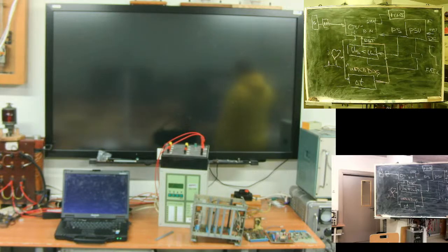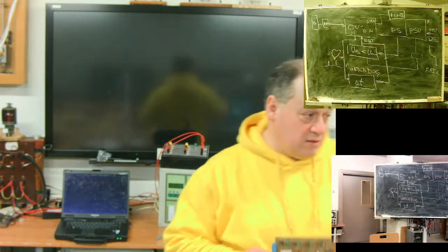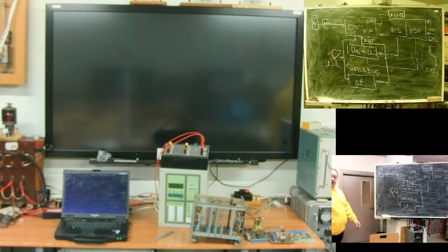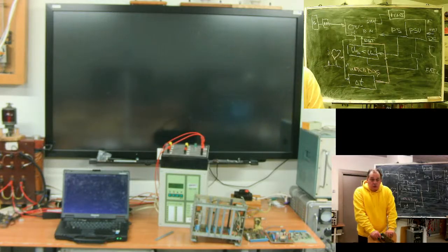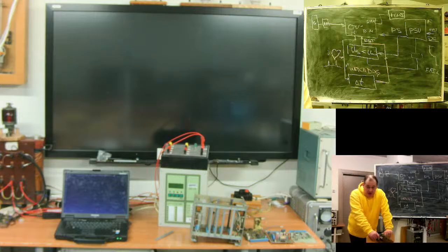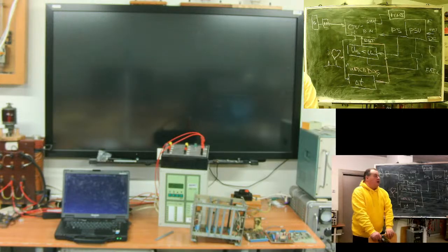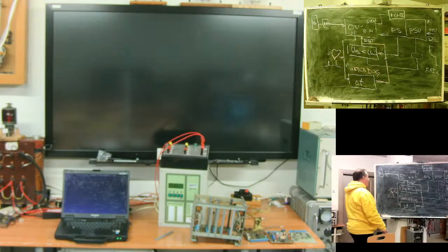The limit of current. It should not calculate fault distance in load regimes because load regimes are not faults. Yeah. But where is the border, the threshold between fault and not fault? It should be programmed, yeah? Line parameters: resistance of direct sequence, resistance of zero sequence, active resistance should be programmed somewhere, yeah? The device should know it.